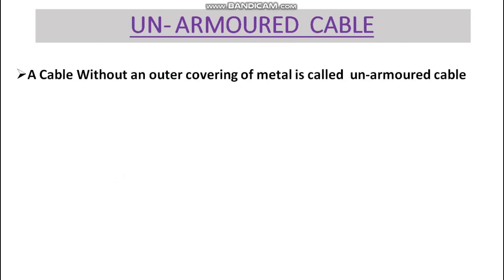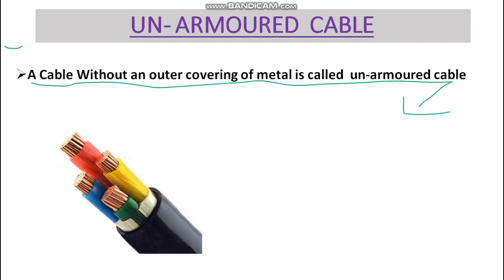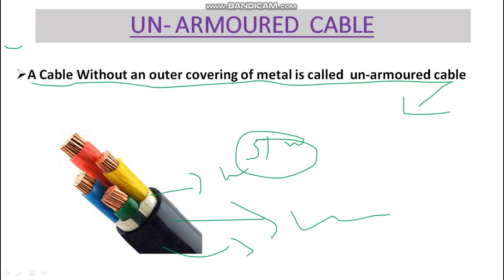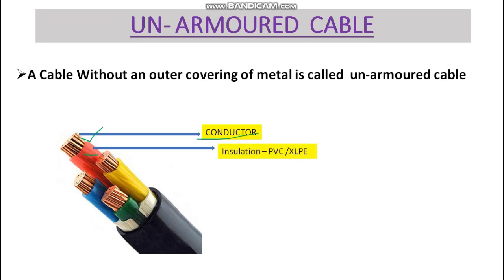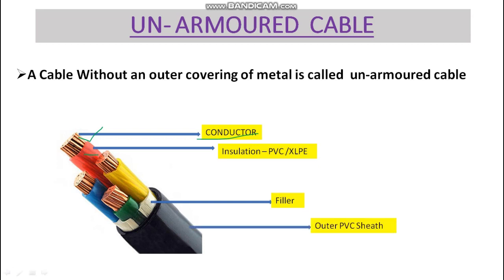Now let's look at unarmored cables. A cable without an outer covering of metal is called an unarmored cable. As you can see here, there is no steel wire over it, so it costs less than armored cable. Its parts are: conductor (copper or aluminium), insulation (PVC or XLPE), filler, and outer PVC sheath. It is used for low-voltage sub-main and distribution purposes internally.